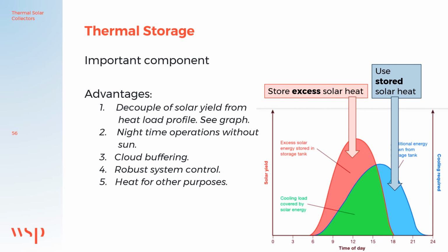Heat or cool storing during the day can be used in periods without sunshine. 3. Cloud buffering: periods of intermittent cloud cover during the day can be bridged in order to maintain continuous system operation. 4. Robust system control: potential temperature fluctuations caused by changing ambient conditions can be balanced out by the storage tank. And 5. Provision for heat for other purposes.